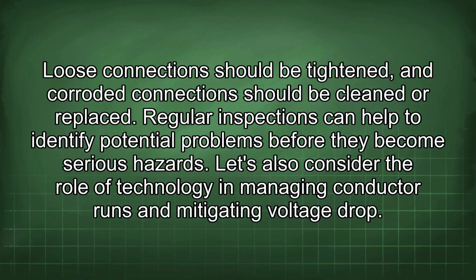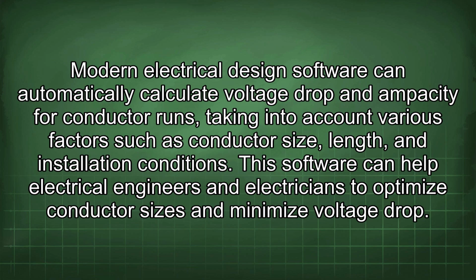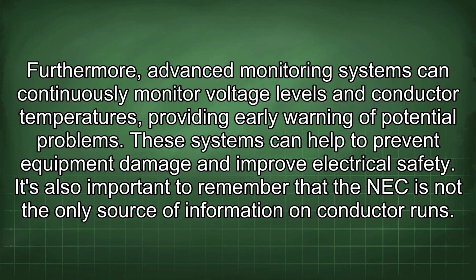Let's also consider the role of technology in managing conductor runs and mitigating voltage drop. Modern electrical design software can automatically calculate voltage drop and ampacity for conductor runs, taking into account various factors such as conductor size, length, and installation conditions. This software can help electrical engineers and electricians to optimize conductor sizes and minimize voltage drop. Furthermore, advanced monitoring systems can continuously monitor voltage levels and conductor temperatures, providing early warning of potential problems. These systems can help to prevent equipment damage and improve electrical safety.